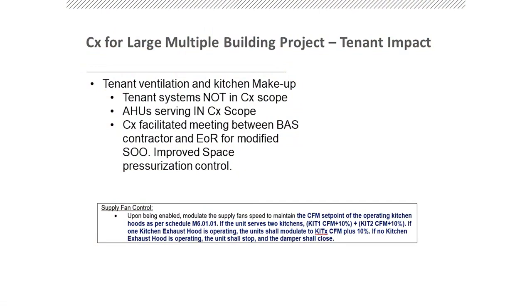In the airside terminal, you have a multitude of different shops, restaurants, and a lot of tenants. It was not in our commissioning scope to commission the AC units or the AC systems for all those shops and tenants, but the air handling units that provided the makeup air and the ventilation air for those tenants were in our scope to commission. And they were having problems that came back to us, because the way the sequences of operation were originally written, they weren't really providing the makeup air, and the ventilation air wasn't maintaining a steady and correct, slightly positive pressurization in the airside terminal.